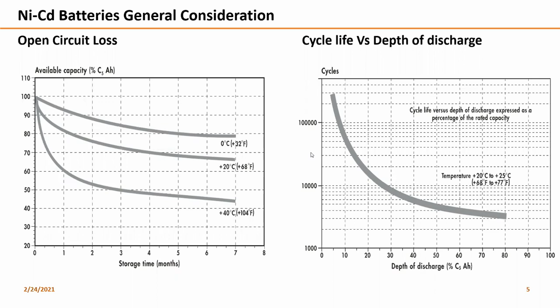This is a major advantage of nickel cadmium batteries: if we operate at the specified charge and discharge parameters, we get much higher cycle efficiency. For example, one cell of lead acid might cost around 25 USD, while nickel cadmium costs around 50. But lead acid needs replacement around every 6 or 7 years in thermal power plants, while nickel cadmium may last 12 or 13 years. So the operating cost of nickel cadmium is much lower than lead acid, and its cycle life is better.